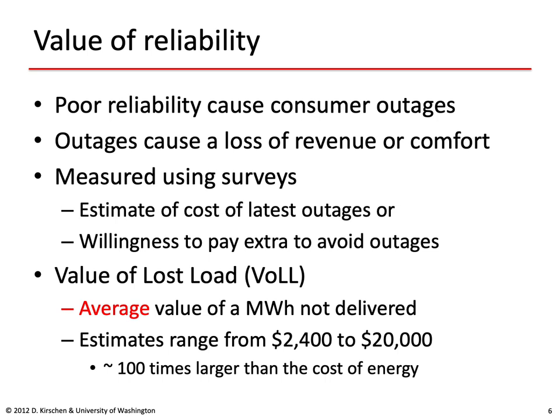This leads to the concept of value of lost load, which is defined as the average value of a megawatt-hour of electrical energy not delivered without notice. The emphasis is on 'average,' because different consumers and different consumer classes will give completely different values to lost load. For example, a semiconductor factory puts an extremely high value on reliability because even very short interruptions result in multi-million dollar losses, while residential consumers put a lower value on interruptions. Estimates of the value of lost load typically range from $2,400 to $20,000 per megawatt-hour, which is 100 times or more larger than the cost of energy.